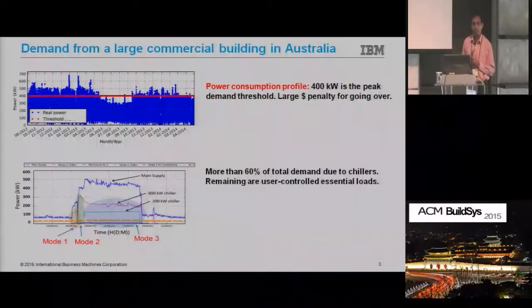They're configured very naively. Basically, the 300 kilowatt unit starts at about 6 to 7 o'clock in the morning, then the 800 kilowatt kicks in about 8 o'clock when people get into work. They have occupancy sensors and temperature sensors, and all these combined make the chiller load spikes really high when people arrive at work around 8am.